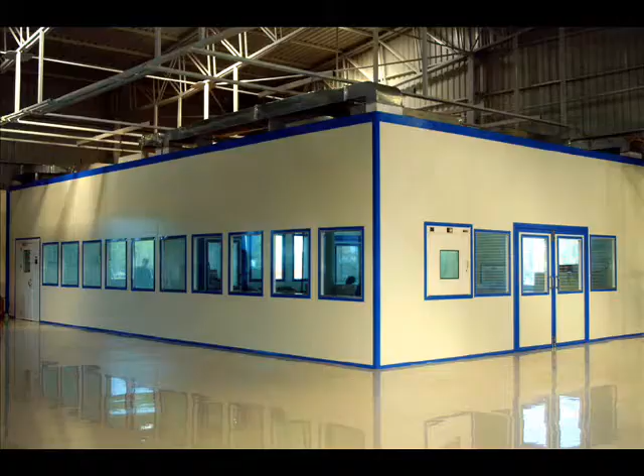Particles may be shed from the body into the surrounding air and pass into the room via special air handling equipment through HEPA filters, as described earlier. The latest filters, called ULPA filters, are efficient down to 0.1 microns in size and work at 99.99998% effectiveness. The room is always kept at a higher air pressure than the surroundings so that the air always moves outward.